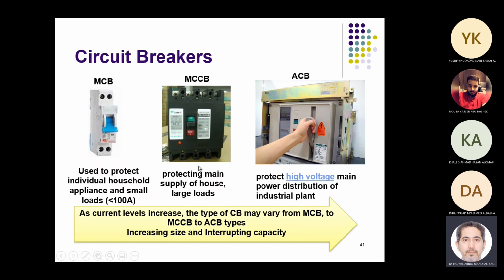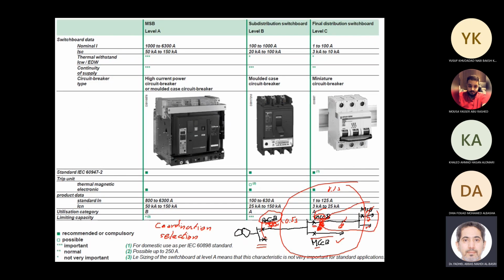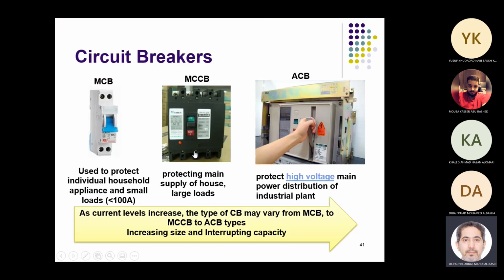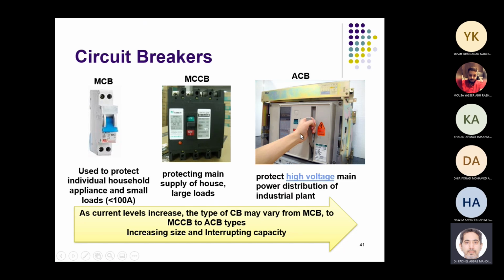And then we have another, bigger breaker called molded case circuit breakers, and this is normally for the main breaker for a house, for example, or larger loads. So they have larger ratings and larger breaking capacity. And for higher, like the main breaker of large buildings or the main feeder from supply, you might see an air circuit breaker that looks like this, or different companies. It's used sometimes for medium voltage, but generally it's for low voltage systems.